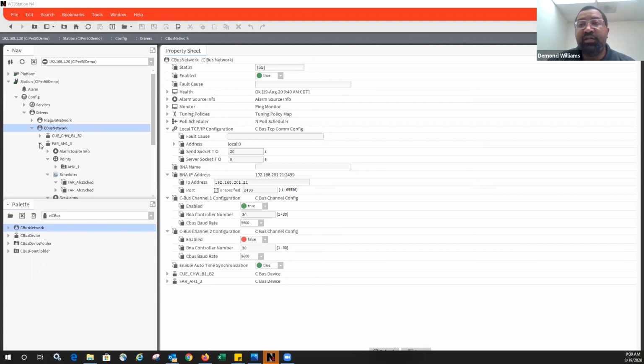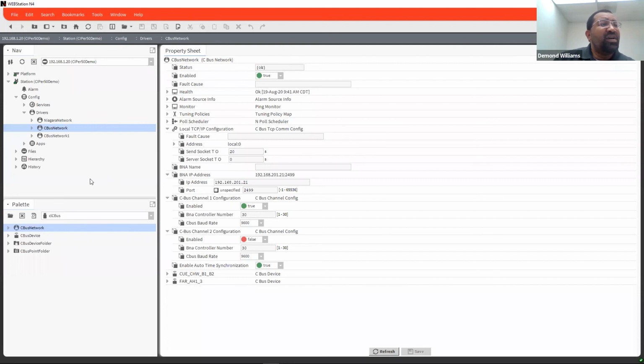So that is one good thing and a plus with this integration: you don't interrupt their existing system until you know that you're done, finished building graphics, getting alarms set up, massaging, however you need the system to be. Once that happens, you can bring your customer in, let them look at the system, and then if everybody's in agreement that you are finished with setting that system up, then you can go in and take the EBI system offline. This device right here, I'm not recommending it as a replace-all type deal.